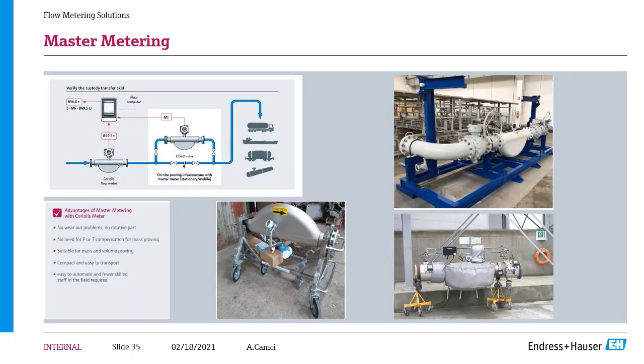I mentioned master metering, so I will give one more example. Master metering is an effective way of ensuring that your duty meter is reading accurately. Here the two meters read the same flow. The master meter has a special calibration, and it is not in daily operation, so it is used on demand. You connect both meters in tandem like this, then you check the flow reading of the Coriolis meter and compare it to the flow reading of the master meter, and the difference is compensated with a so-called meter factor.